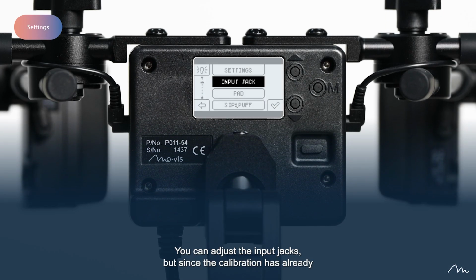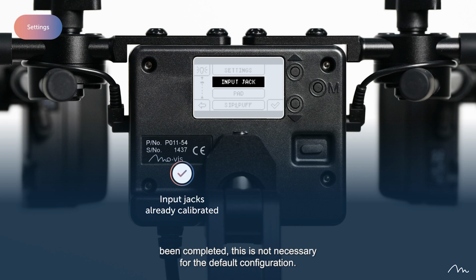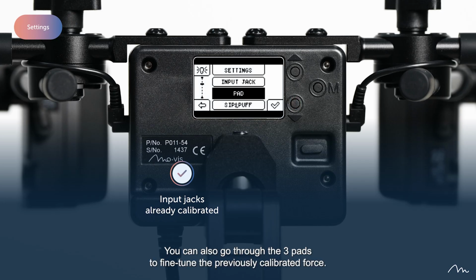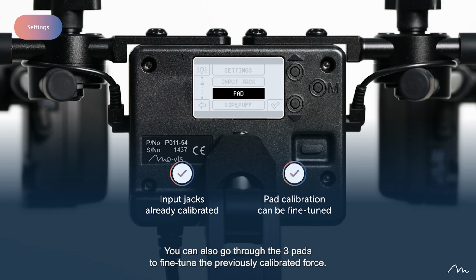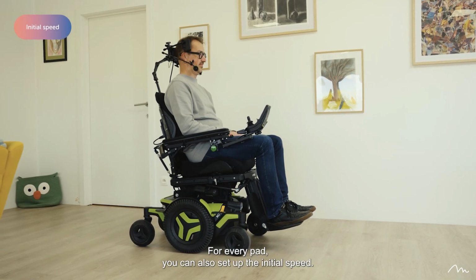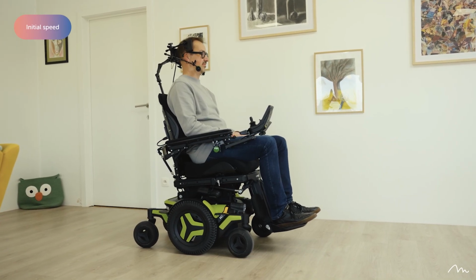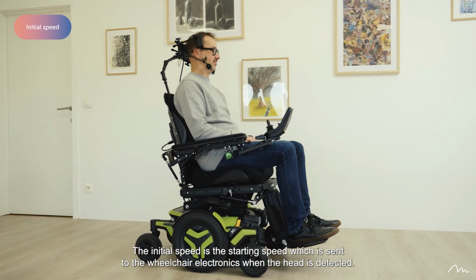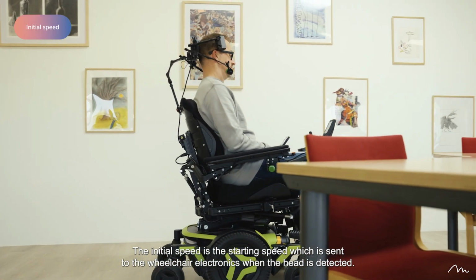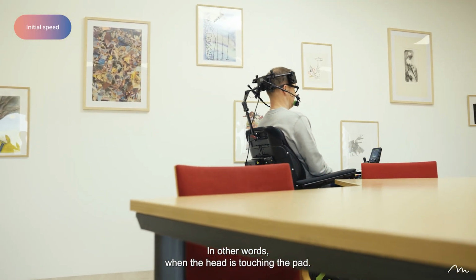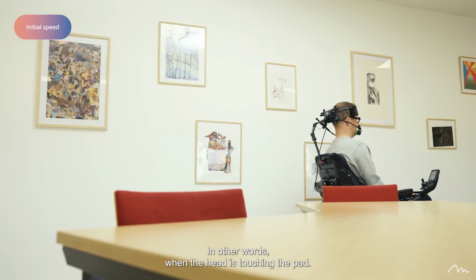You can adjust the input jacks, but since the calibration has already been completed, this is not necessary for the default configuration. You can also go through the 3 pads to fine-tune the previously calibrated force, for example, if the user indicates that they need to press too hard to drive comfortably. For every pad, you can also set up the initial speed. The initial speed is the starting speed, which is sent to the wheelchair electronics when the head is detected. In other words, when the head is touching the pad.